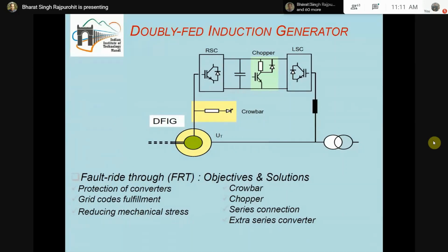Fine. In this case, DFIG, you are able to see this is connected to the grid, and in the rotor side there are two converters known as back-to-back power electronic converters. One is the RSC, known as the rotor side converter, and another one is the LSC, known as the line side converter. So what is this converter and what is the control objective of this converter? The rotor side converter is able to inject or take power out from the rotor of this DFIG, and it is able to control the speed of this doubly fed induction generator based on the wind speed, and hence it will be able to make this system a variable speed system and operate a maximum power point tracking algorithm also, and control the stator active and reactive power.